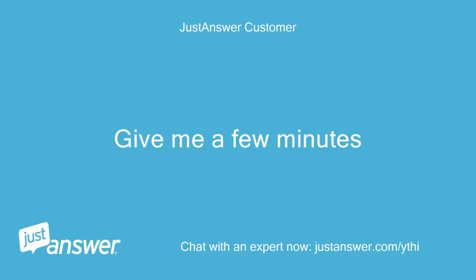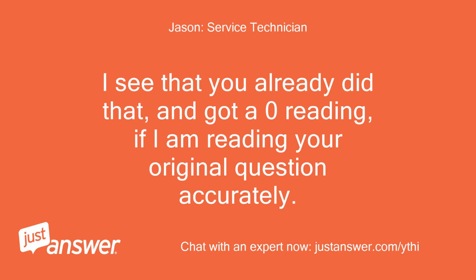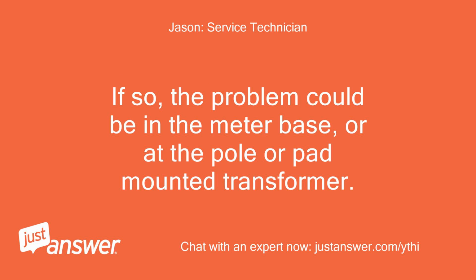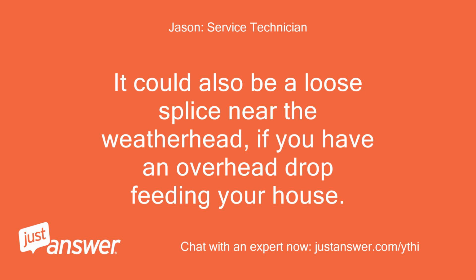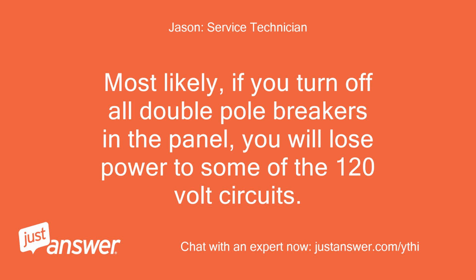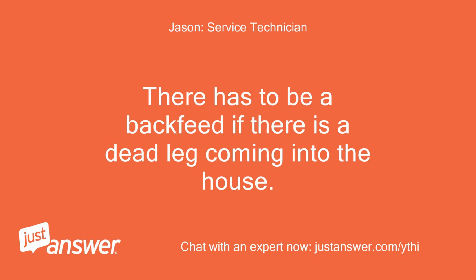Give me a few minutes. I see that you already did that and got a 0 reading, if I am reading your original question accurately. If so, the problem could be in the meter base, or at the pole or pad-mounted transformer. It could also be a loose splice near the weatherhead, if you have an overhead drop feeding your house. Most likely, if you turn off all double pole breakers in the panel, you will lose power to some of the 120-volt circuits. There has to be a backfeed if there is a dead leg coming into the house.